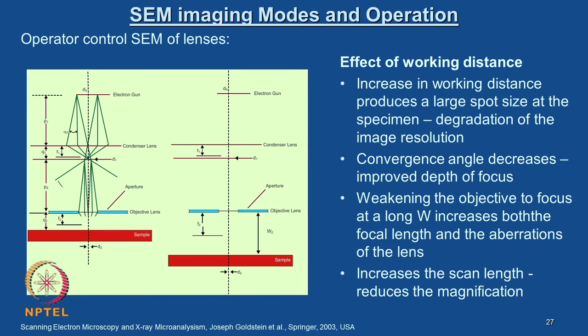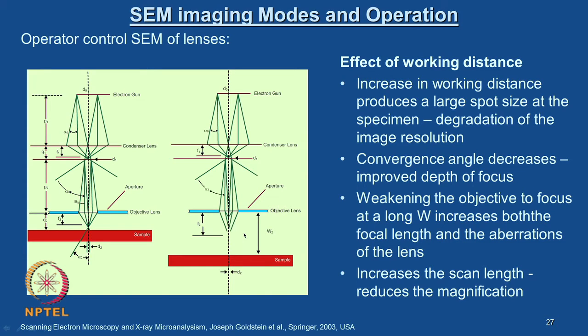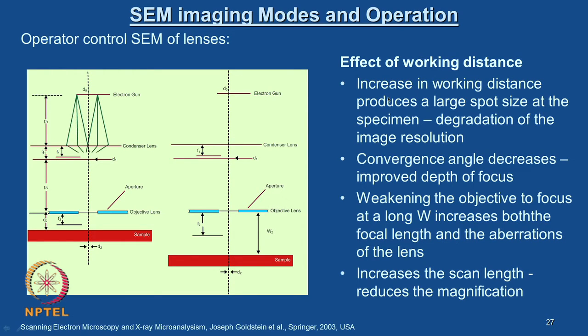The next parameter is the working distance. The working distance is the distance between the final aperture and the specimen surface. You can clearly see the effect of working distance from these two schematics: if you increase the working distance, you are increasing the probe size, which will have a significant effect on resolution. Increase in working distance produces a large spot size at the specimen, which causes degradation of the image resolution.